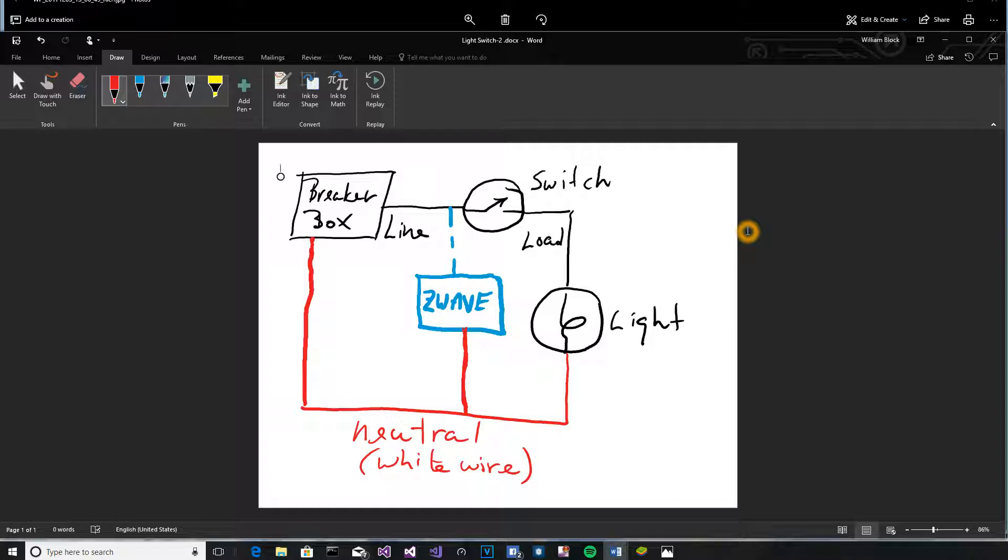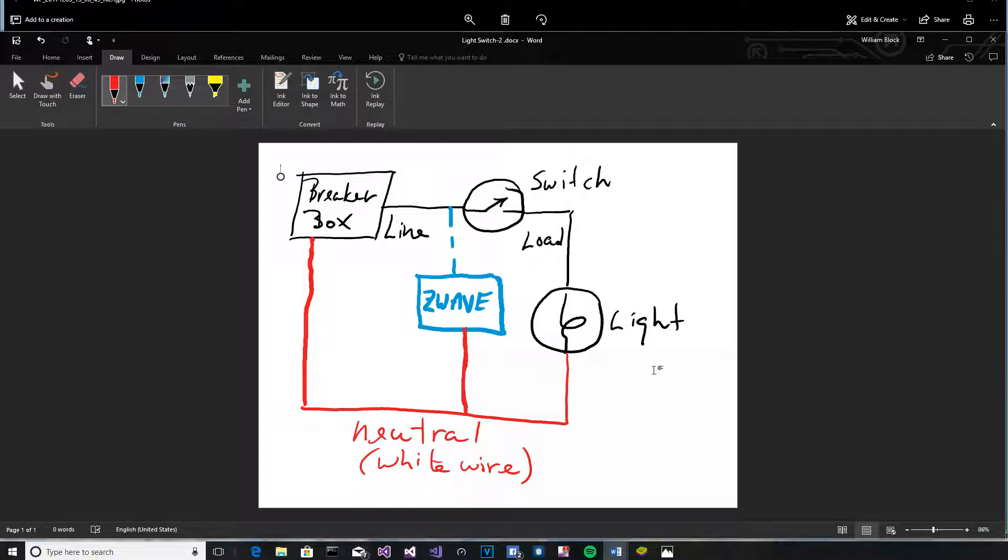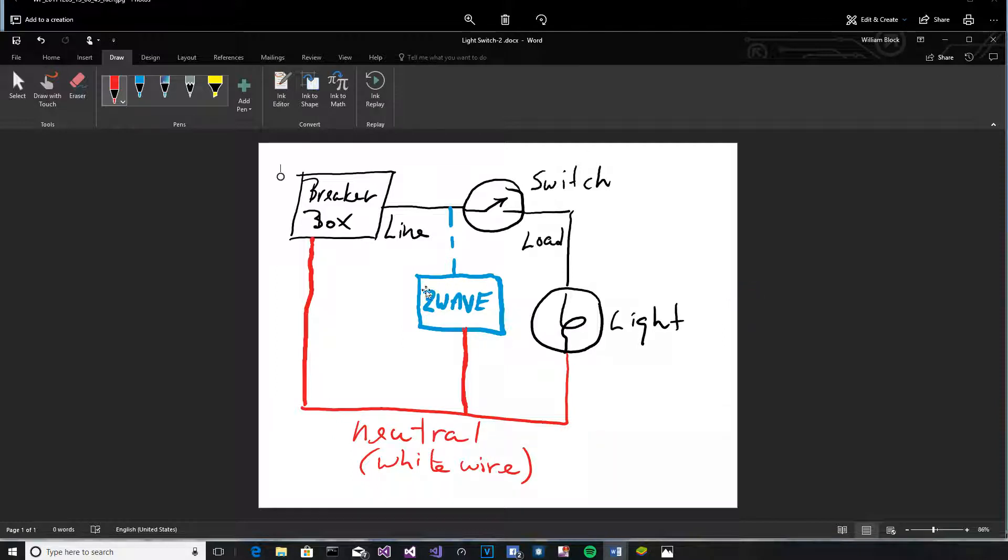And if you wire it that way, then your switch is not going to work. So, I wanted to point out with a simple diagram what this is all about. And the reason the neutral becomes important now is because the switch itself becomes part of the load. It has to have a return path so that it can complete its own circuit.